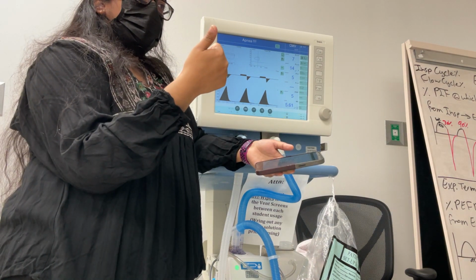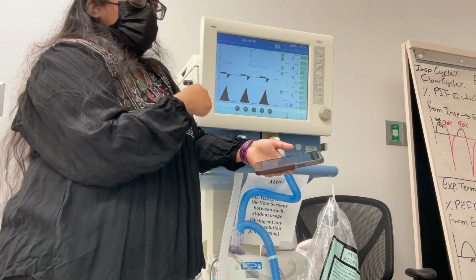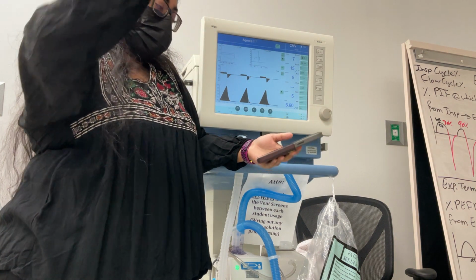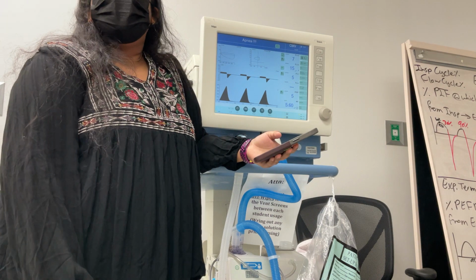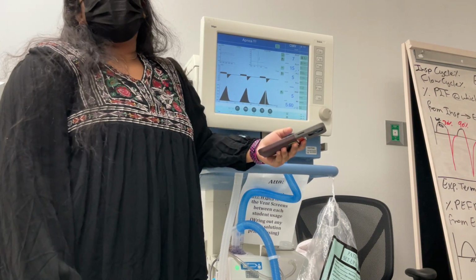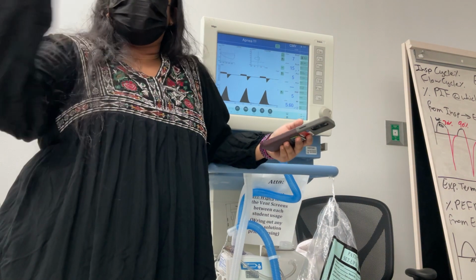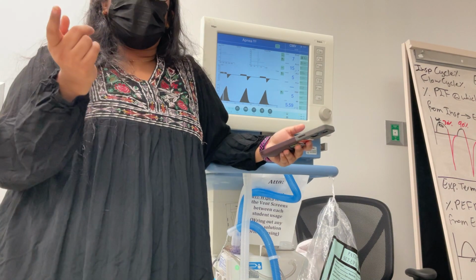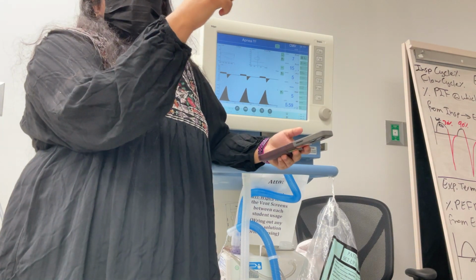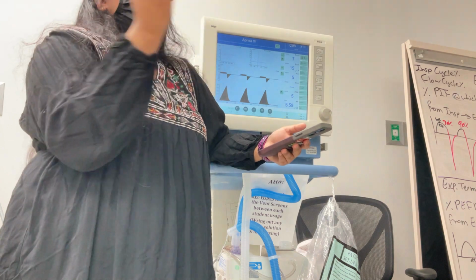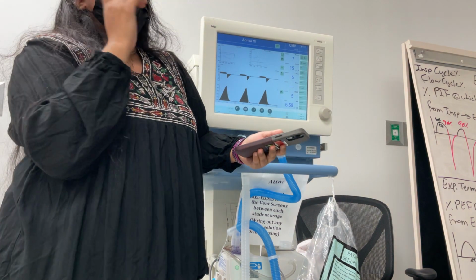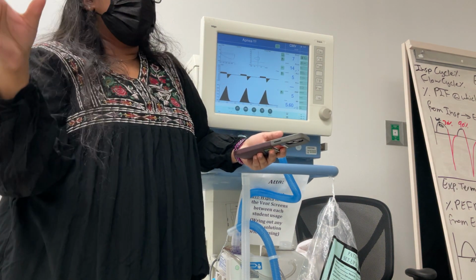Volume guarantee on your pressure modes, you won't have that on this ventilator, only on the V500. On your pressure modes, to make your pressure mode into PRVC, you have volume guarantee turned on, only on the V500. On the XL, there's no option for volume guarantee. So only your volume modes can be turned into PRVC with autoflow.